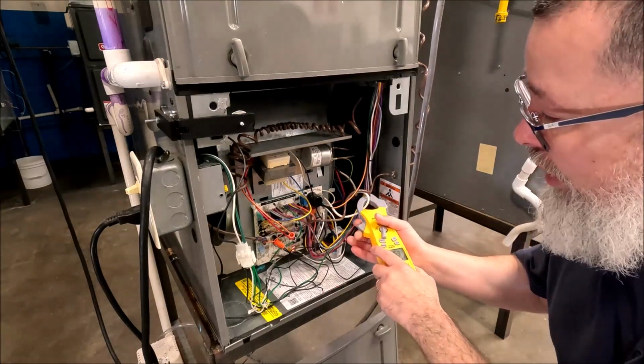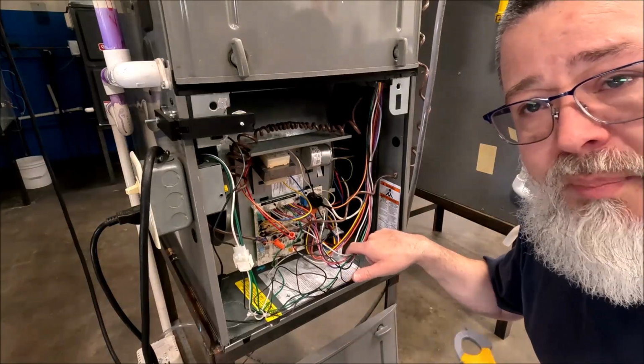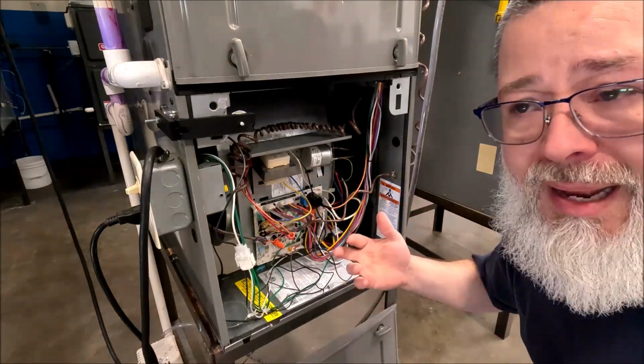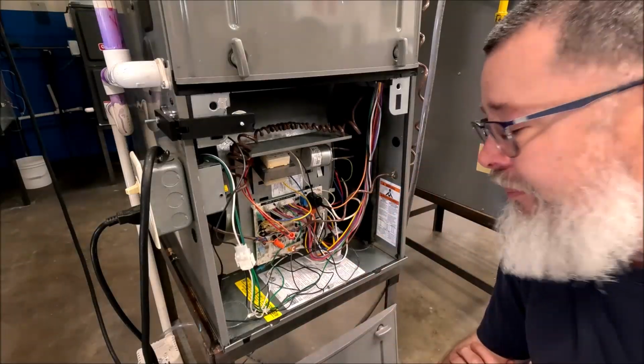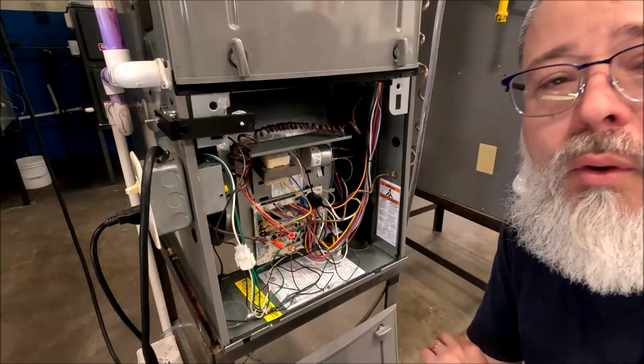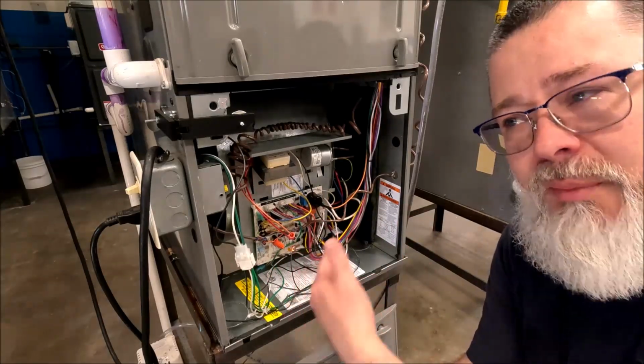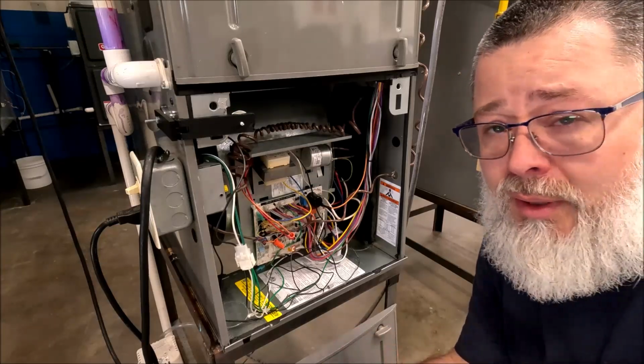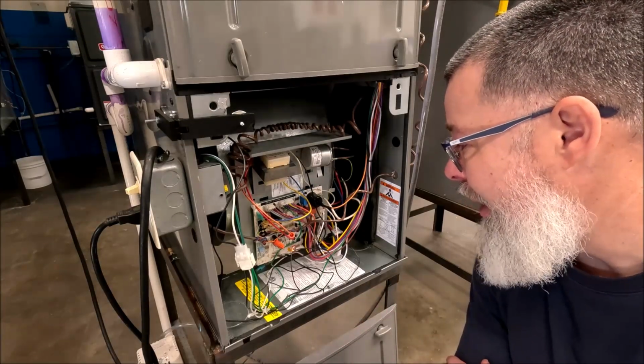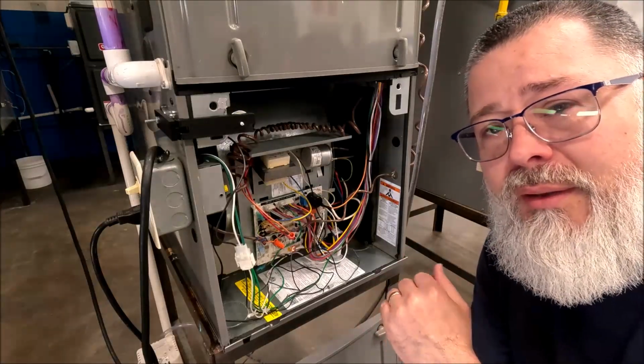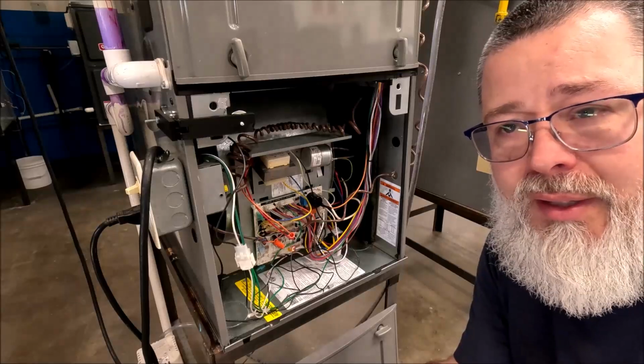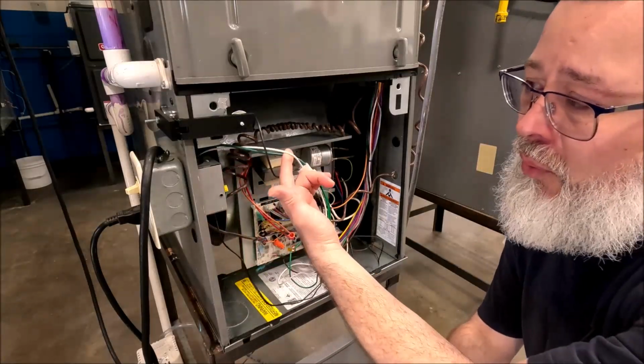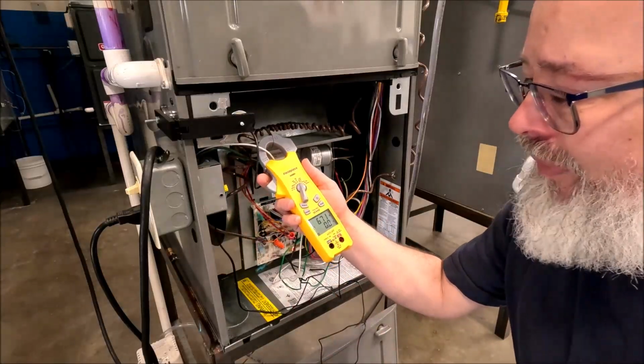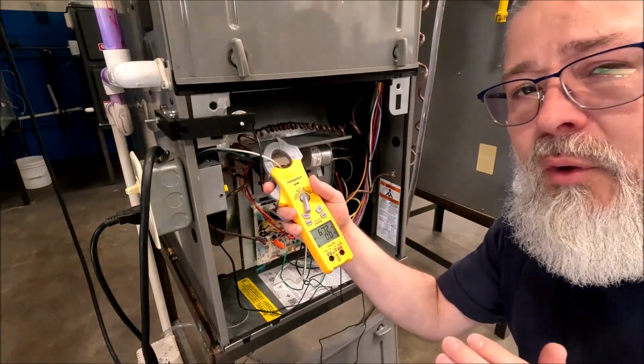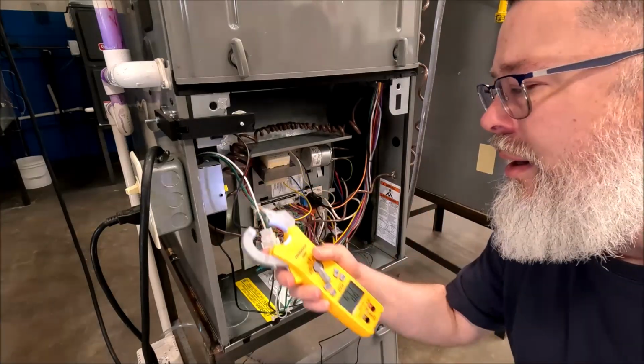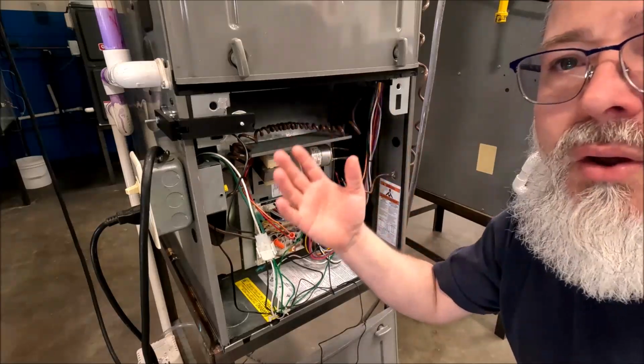6.5 amps. So even though I've got a multiple speed PSC motor, high, medium, low, medium, high, medium, low, whatever, we don't know which one it is, or let's just pretend you didn't know which one it is. If I'm in heat mode, it should be on the heat speed on the furnace board. If I'm in cool mode, it should be on the cooling speed. But no matter what, I'm always using the neutral because that is the return part of that circuit back to the power source. And here's my neutral wire right here. And even if I clamp here, I'm pulling 6.7 amps. So that's a little bit more than what I just pulled for the blower motor. But that's because we've got things like the primary side of the transformer that's also in this system.